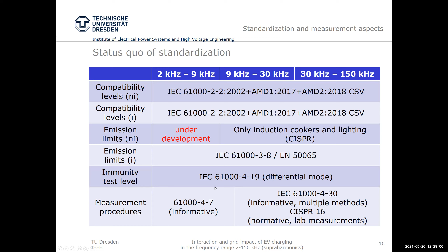Well, if you have limits, then you also have to measure them reproducibly and comparably. And that's the next challenge that we face. For the frequency range 2 to 150 kilohertz, strictly no normative method exists for grid measurements. There is only a normative method, CISPR 16, for the measurement of equipment emission in the lab. But for the 2 to 9, we only have 61000-4-7 with an informative annex. And for the 9 to 150, it's even more challenging.